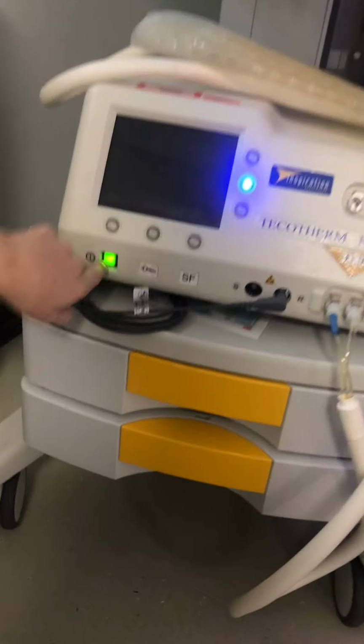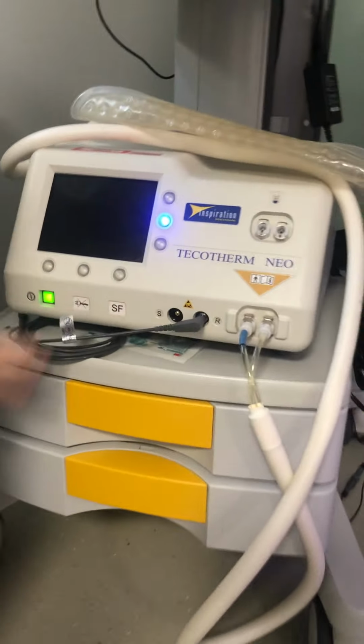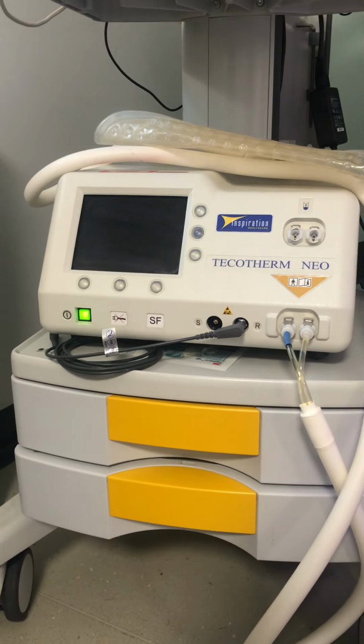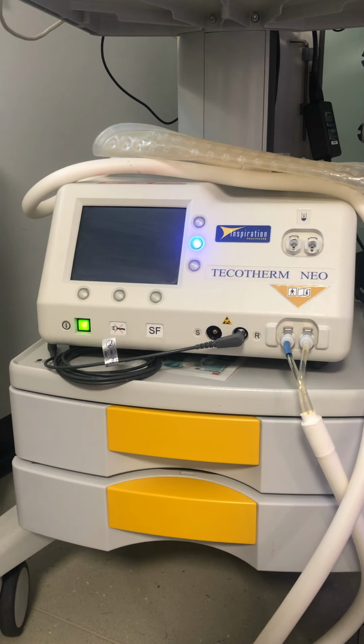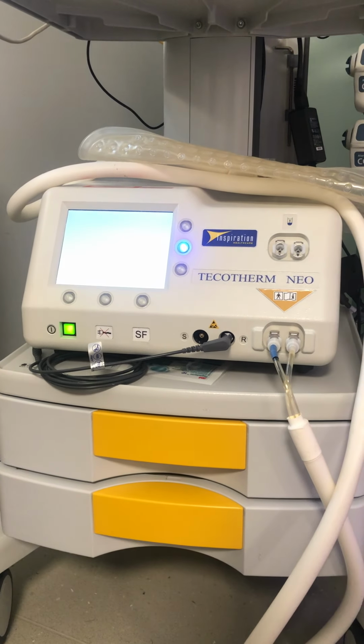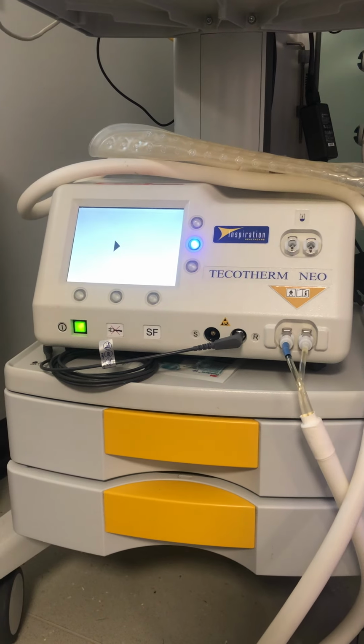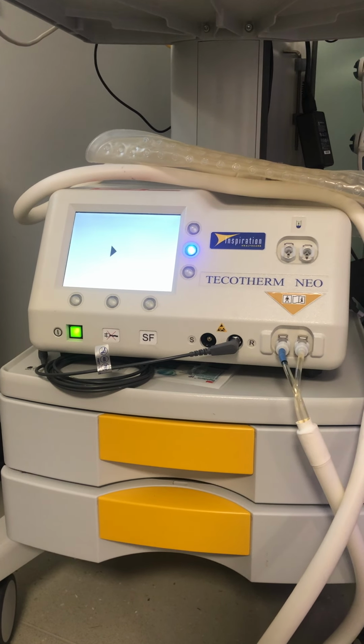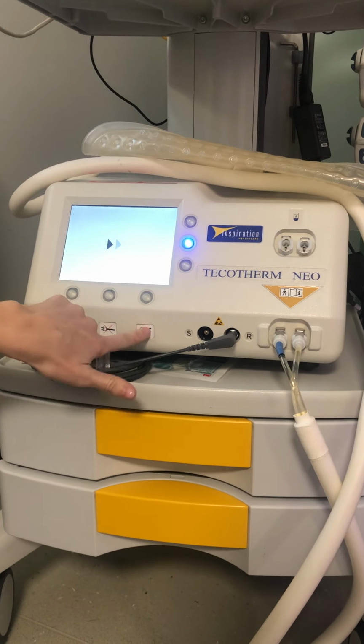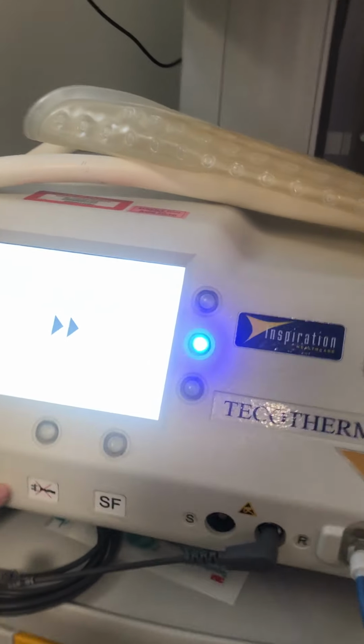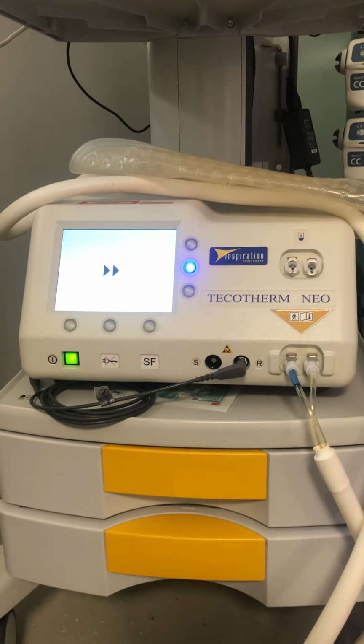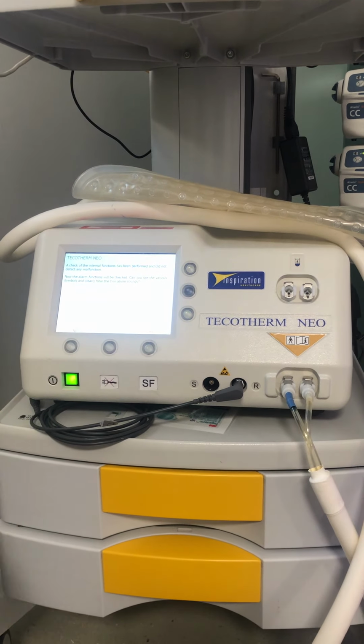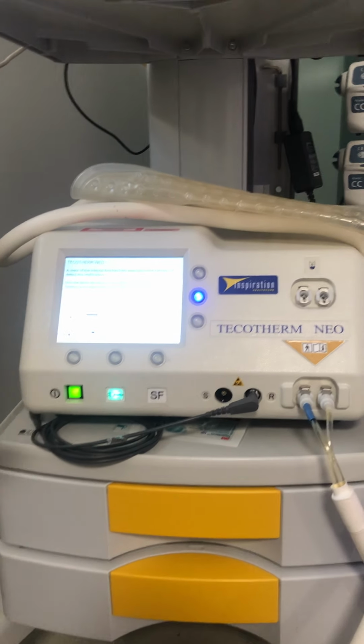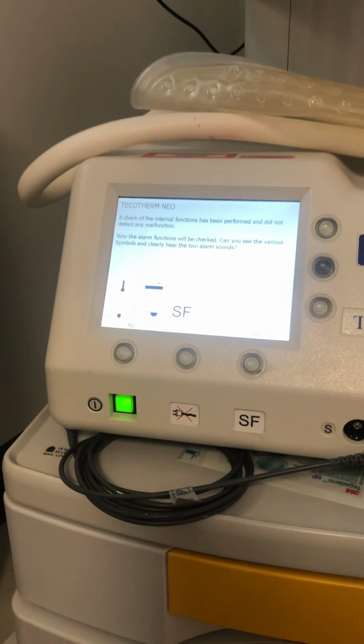I've got to be quick since there's only so long to upload to WhatsApp. First things first, push the big green button to turn it on, and the blue lights will come on. All the alarms will start going off, which is normal, and you'll go through two sets of alarms before it lets you silence it, which is just a safety feature. Once it boots up, you should see all the different lights and buttons flash to alert you if anything's wrong with the machine. If the sound wasn't working, you could at least see flashing buttons, but don't use it unless you can hear the alarm. That's the first one, and that's the second one.